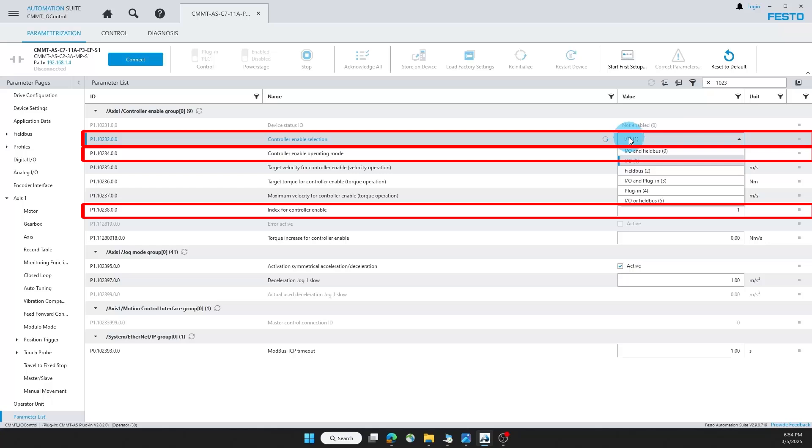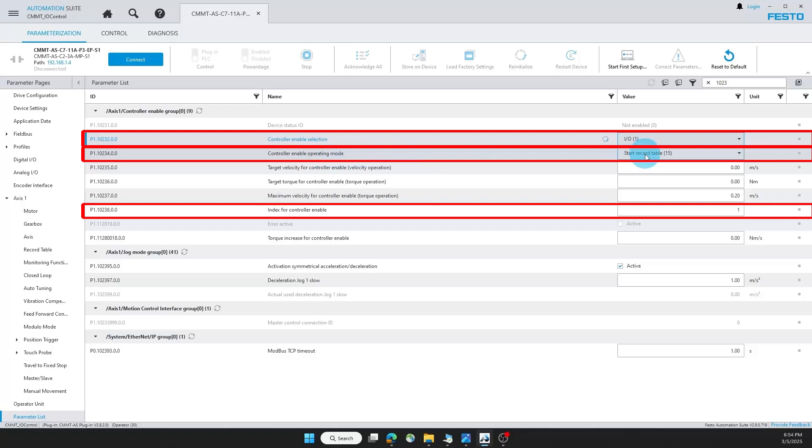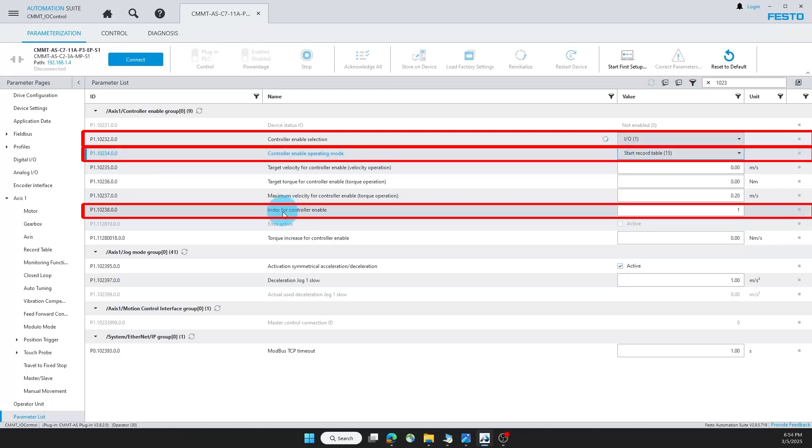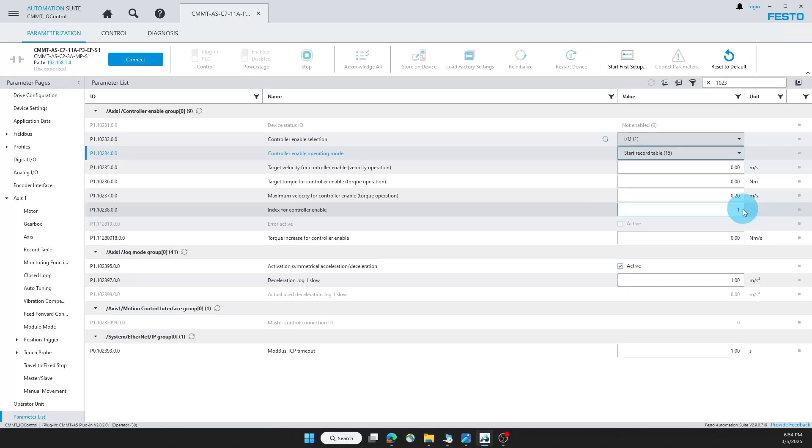For instance one, controller enable selection, we'll make sure it's set to I.O. This is the value I recommend. Controller enable operating mode, we'll make sure this is set to start record table, although originally it's set to position. And we also want to make sure this index for controller enable is set to one, although there's an exception that I'll describe later in this video why you may want to change this value.